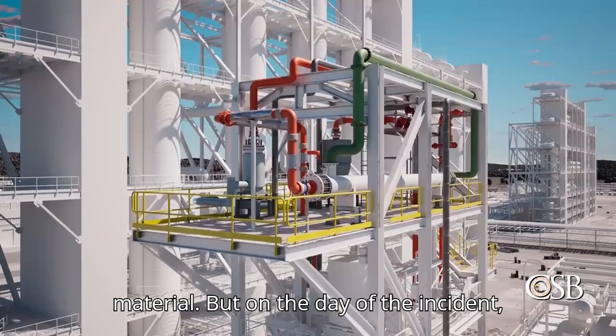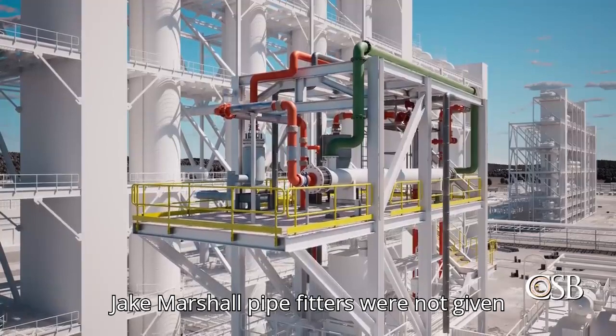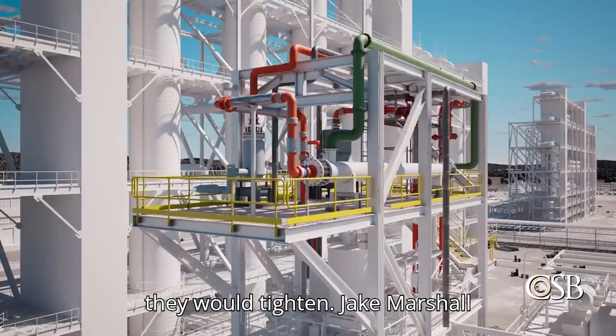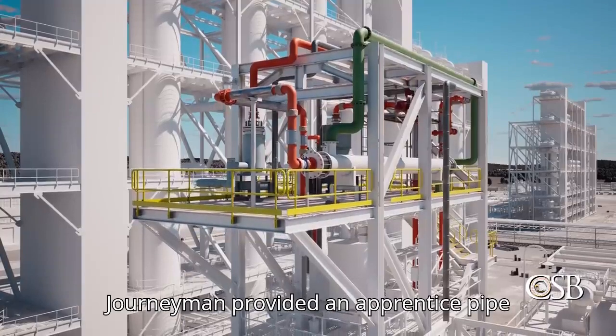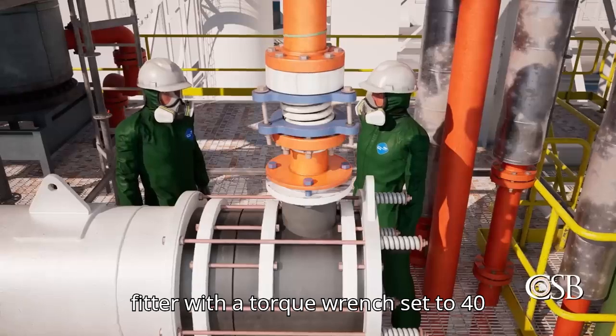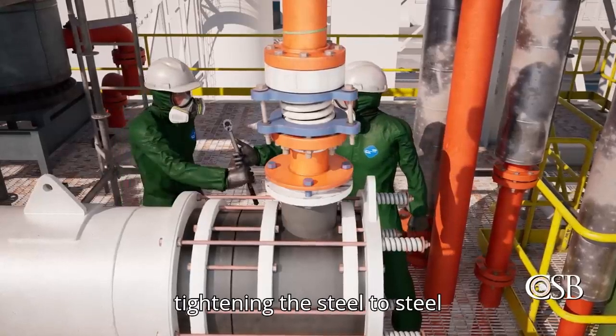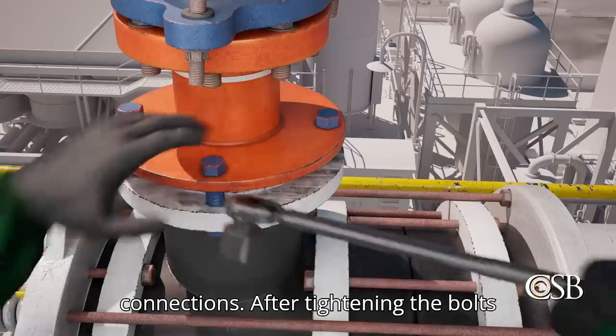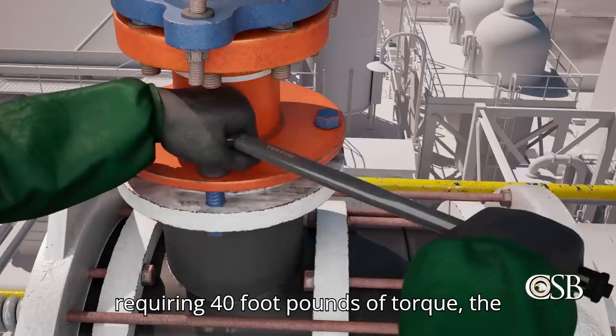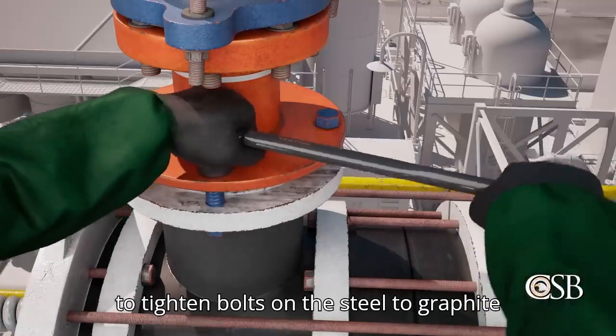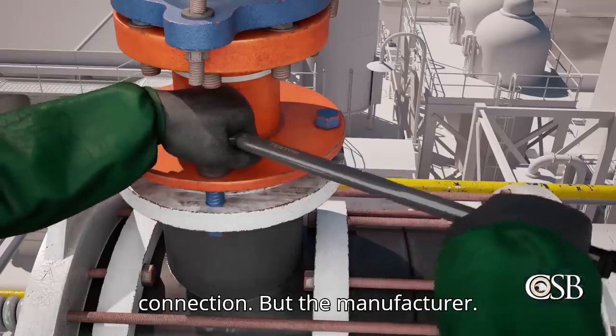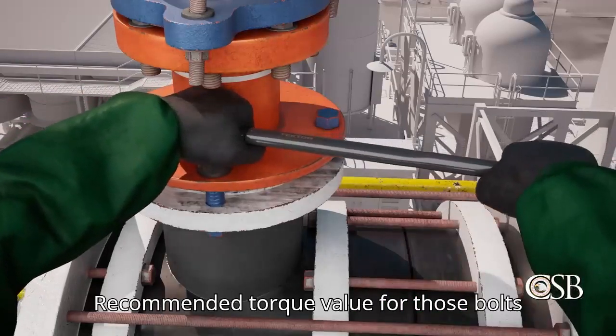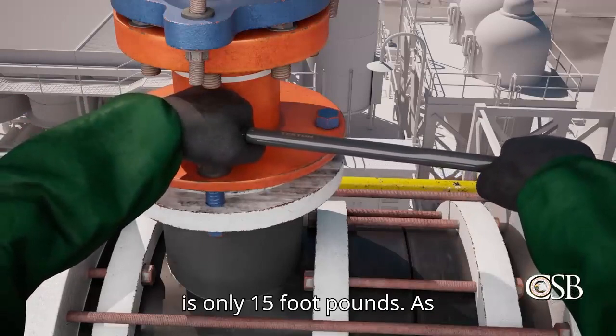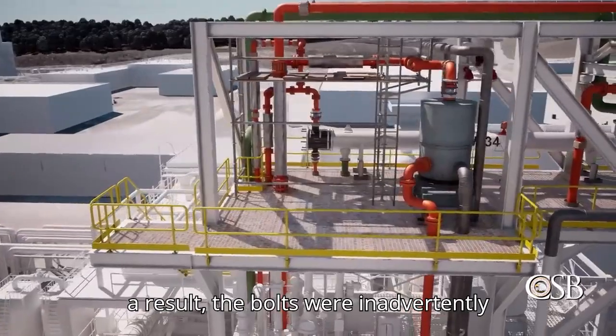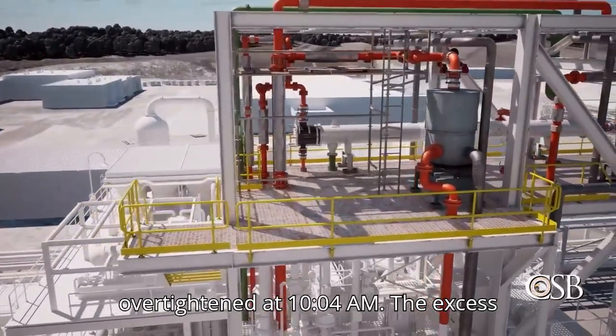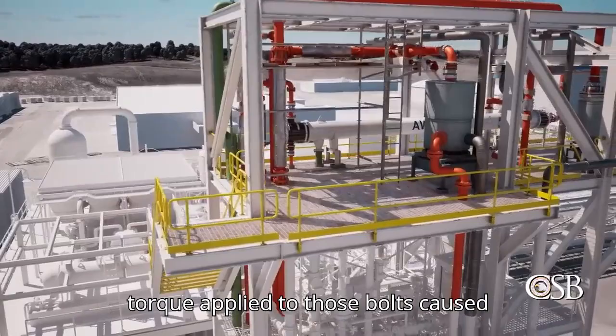But on the day of the incident, Jake Marshall pipe fitters were not given written specifications for every bolt they would tighten. A Jake Marshall journeyman provided an apprentice pipe fitter with a torque wrench set to 40 foot-pounds, which is the setting for tightening the steel-to-steel connections. After tightening the bolts requiring 40 foot-pounds of torque, the pipe fitter then used the torque wrench to tighten bolts on the steel-to-graphite connection. But the manufacturer recommended torque value for those bolts is only 15 foot-pounds. As a result, the bolts were inadvertently over-tightened. At 10:04 a.m., the excess torque applied to those bolts caused the heat exchanger to crack.